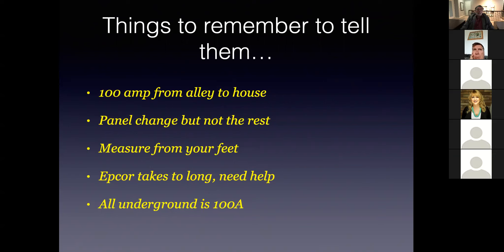Underground services. Underground services came out approximately 1968, 1969, 1970, and are always a minimum of 100 amps. Overhead can be anywhere from 35 amps back in the 20s and 30s to 60 amp. Overhead services can also be 100, because that came out about 1963 or 1964. But what we use as a rule of thumb is anything 1965 and prior could be a 60 amp service.